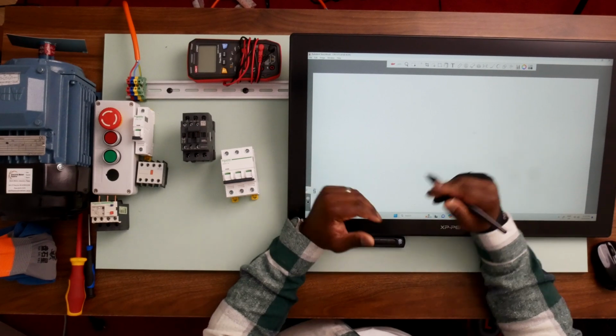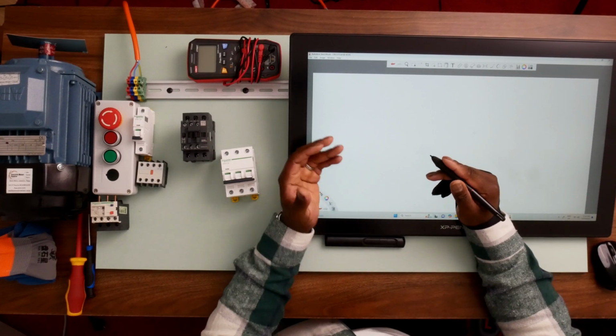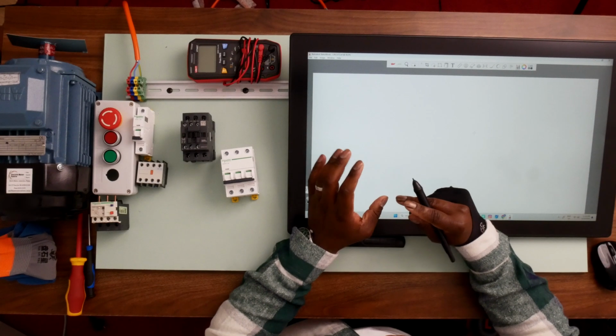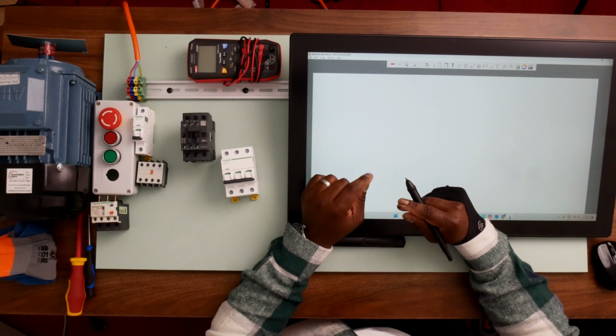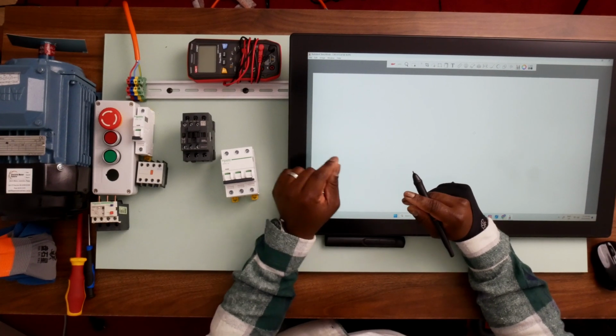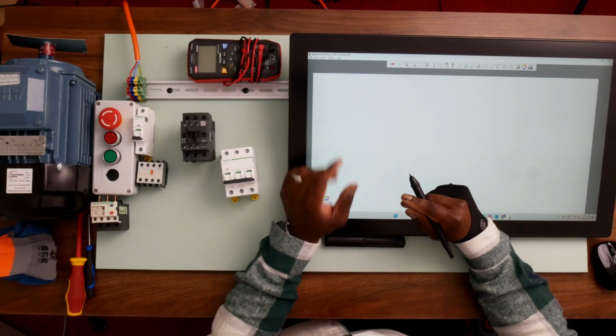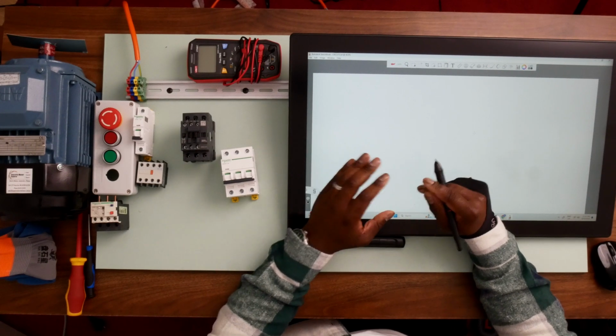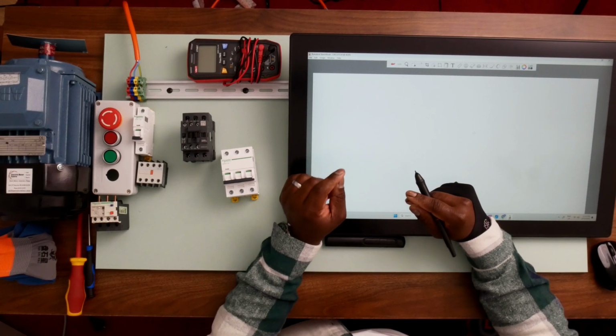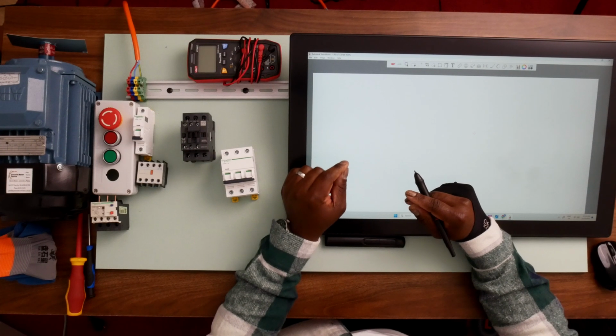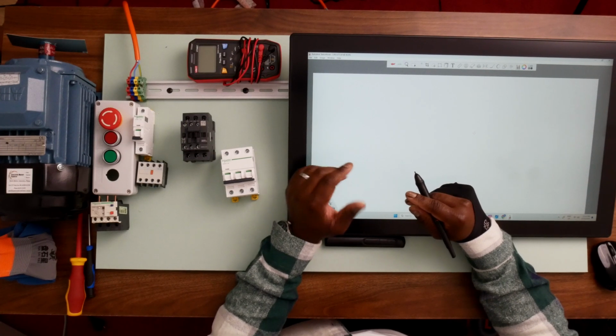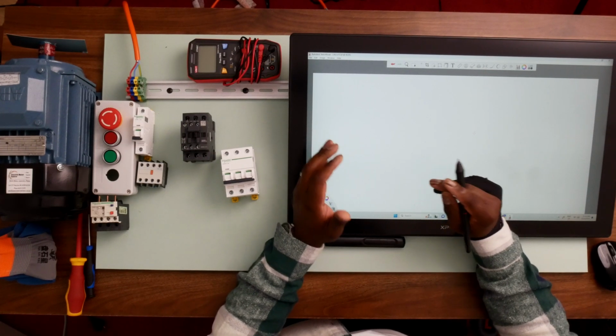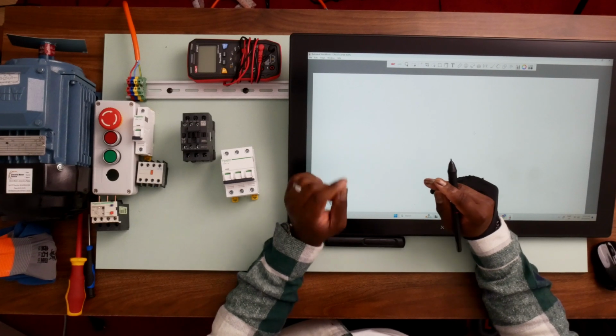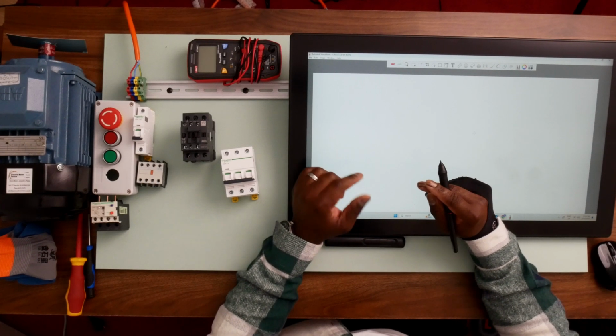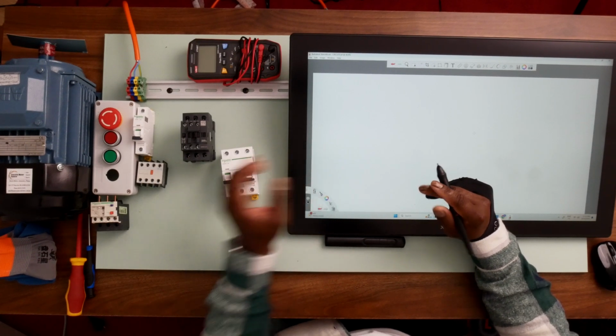Now, the next component in our control circuit is a contactor. The contactor is part of both the power and control circuit. The contacts on the power circuit are designed to handle the large switching currents. Always check manufacturer specifications to make sure your selected contactor can handle the inrush currents of your electric motor. The normally open auxiliary contacts are either built-in or clip-on.